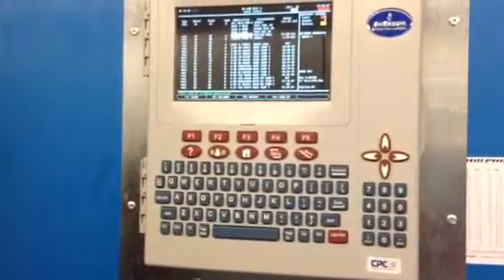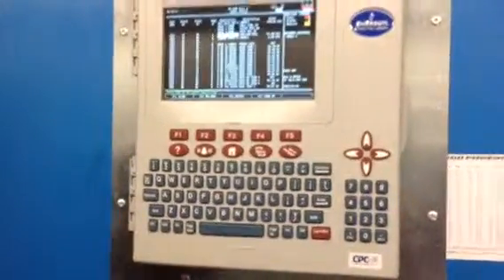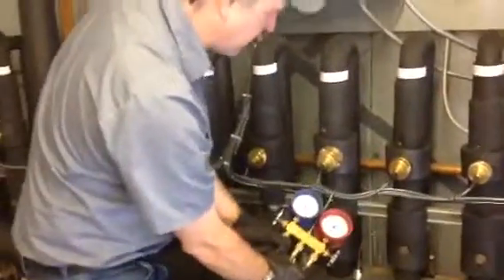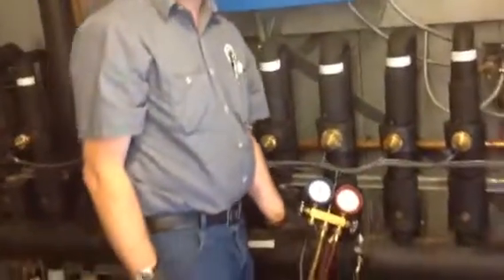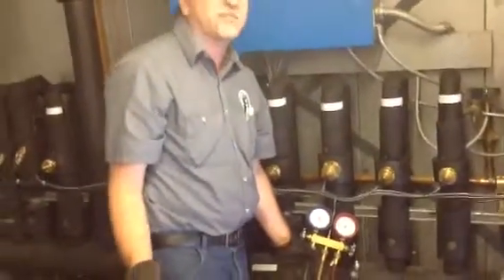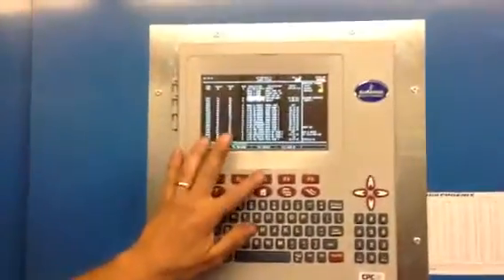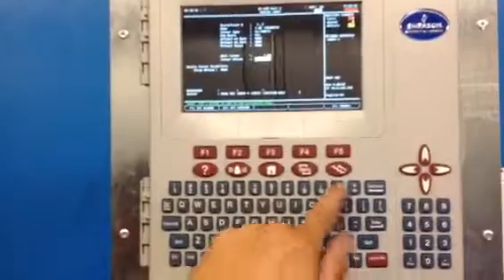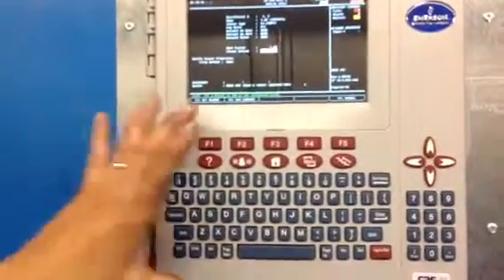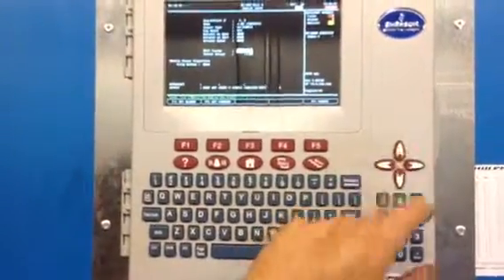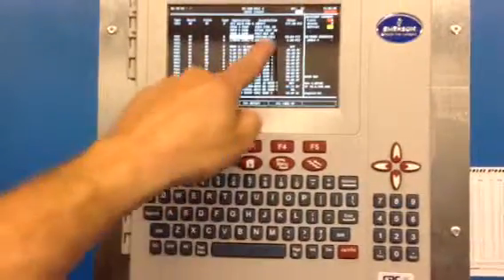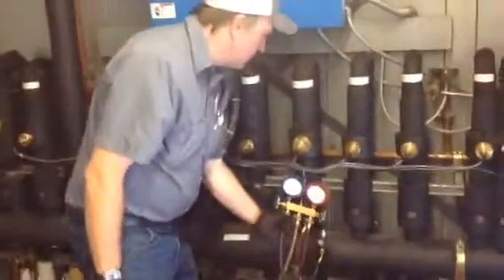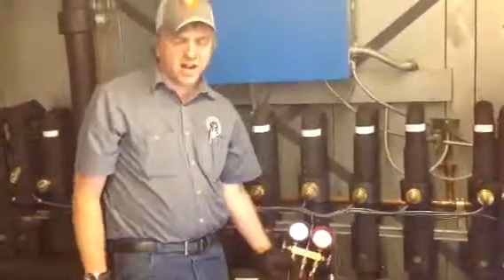51.9 pounds, about 52 pounds. So let's go check our gauges one more time. Our gauges are reading about 51 pounds, so we know we have a 1 pound offset now. Offset, -1, because we had to back up one, this was reading high. Now we're showing 50.8 pounds. Look at our gauge, we're right on the money.